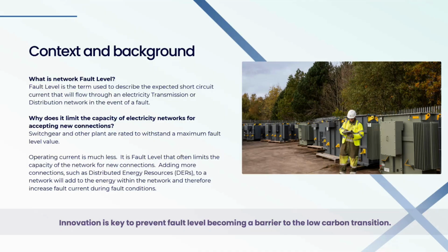Just to start with, I think it's important to make sure everyone has a common understanding of what we mean when we talk about network fault level. Fault level is the electrical term that we use to describe the expected short circuit current that will flow through a network in the event of a fault. It's got nothing to do with how many faults we experience on the network. It's all about what happens within the network when we actually get a fault.